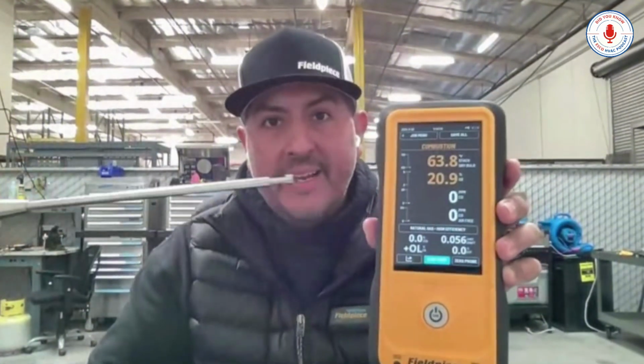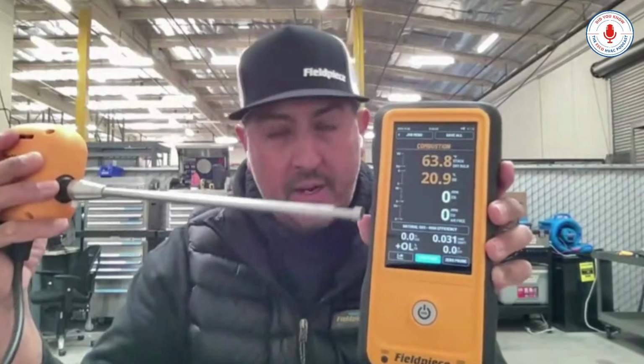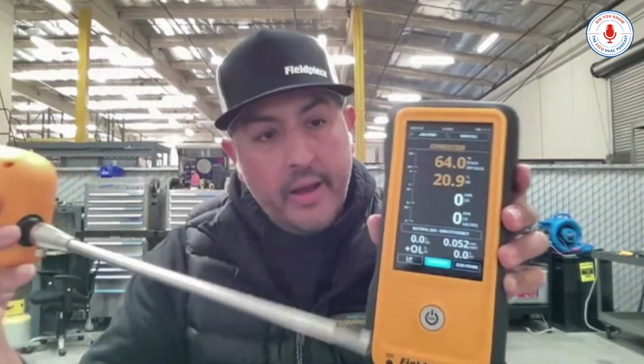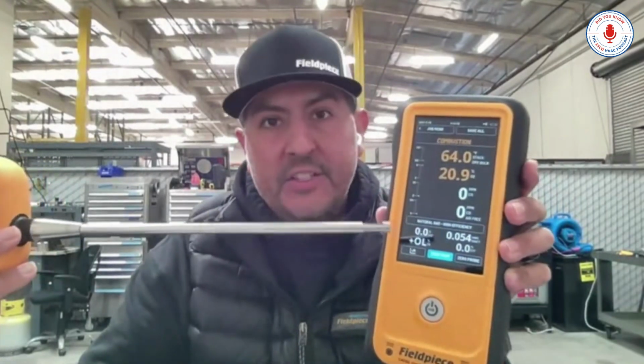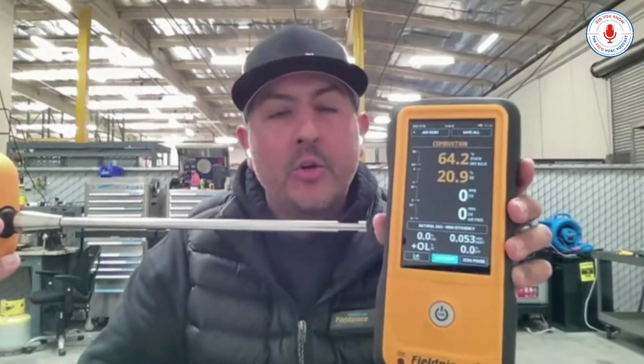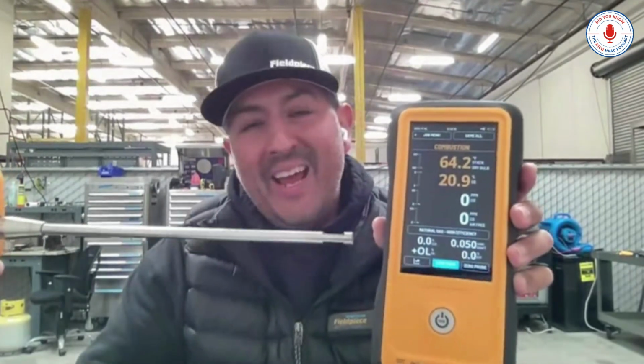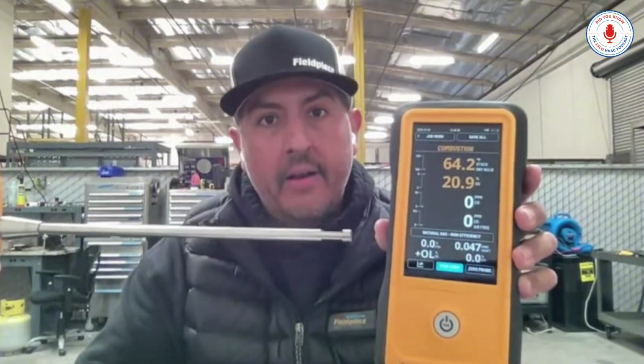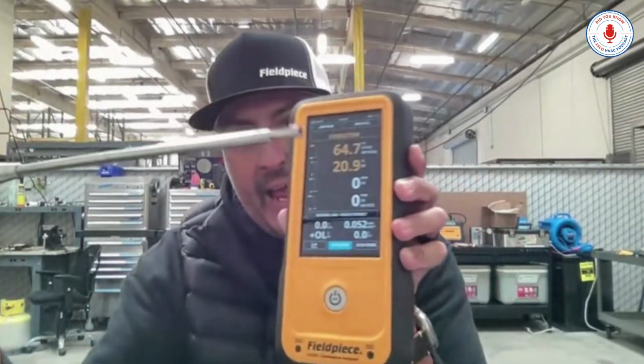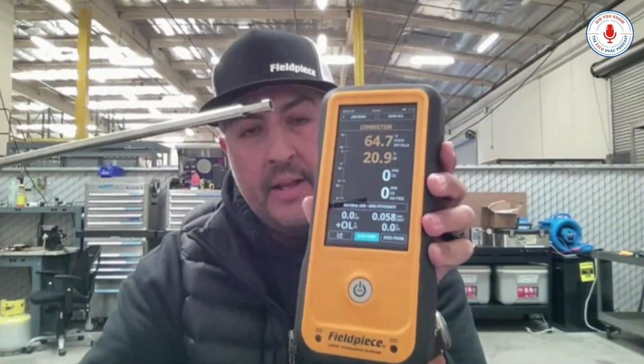Okay. So now that we're set up and ready to begin sampling gases, the location where we sample the combustion gases is very important. Let's just stick with this high efficiency system. Generally, you want to install a test port at least 12 to 18 inches above the inducer fan, right? You want to make sure that you're not too close to the box, but that you give the combustion gases time to settle and get to a steady state in the flue. You bet. Okay. So then you insert this into your flue, and your combustion analyzer is now sampling the combustion gases.